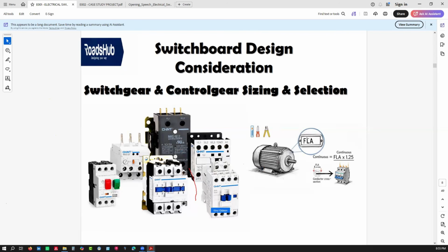So how do I go about that? Do I increase the size of the breaker, or do I just size the breaker based on the inrush current? We have options. You can go on different curves of the breaker. We have curve D, curve B, curve C for MCBs, and they trip with different timings. So if an inrush current takes a short time to happen, and you take a breaker that has a lower switching time than the time the motor runs when it starts, you will be tripping that motor all the time.